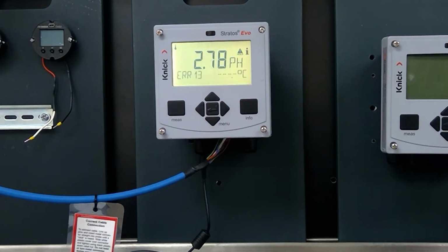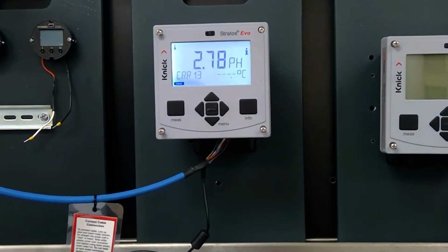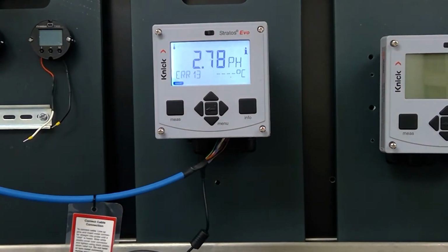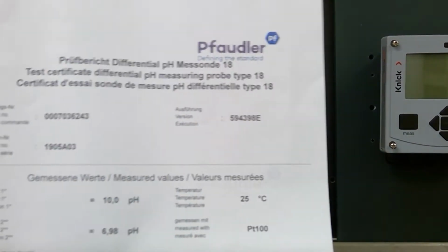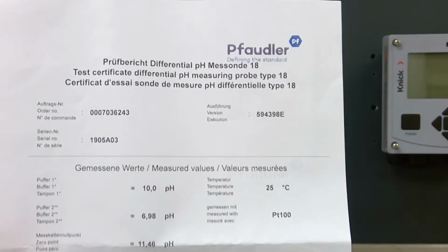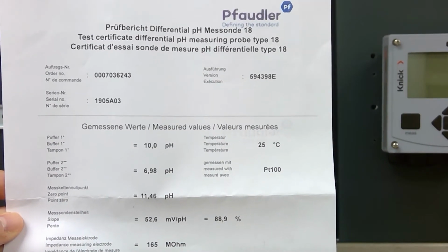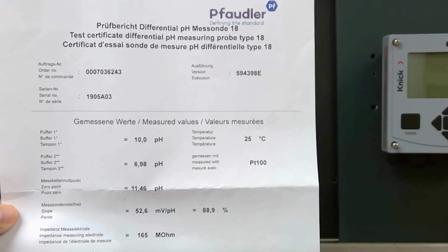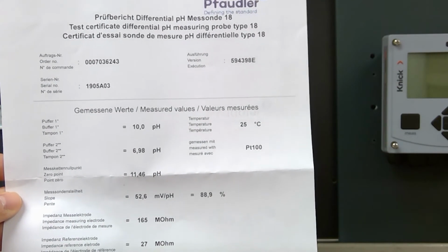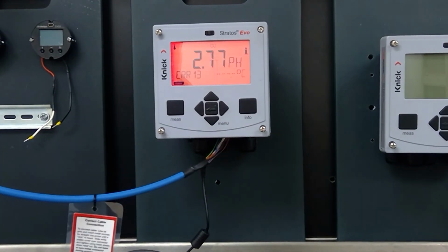Now, when you first get your pH probe, your Type 18, there's a couple of things that you should understand. In the box, you're going to have a test certificate. It's going to look just like this, and each Pfaudler Type 18 has a unique test certificate with important information that we're going to need to properly configure this pH electrode. The second thing you're going to want to do is prep the sensor as well, assuming that you're going to do calibration shortly after you do the configuration.